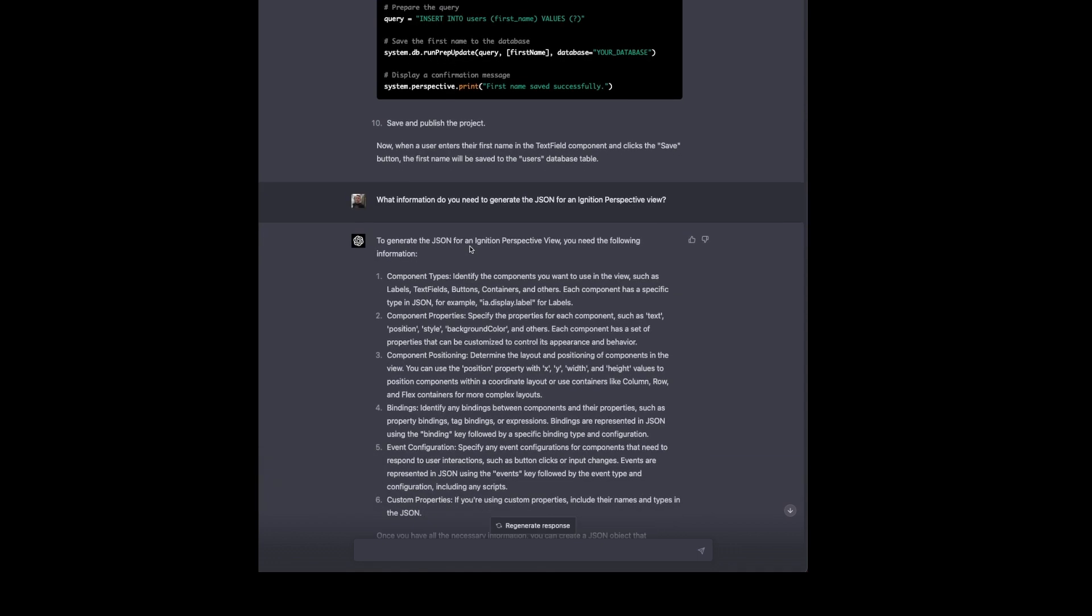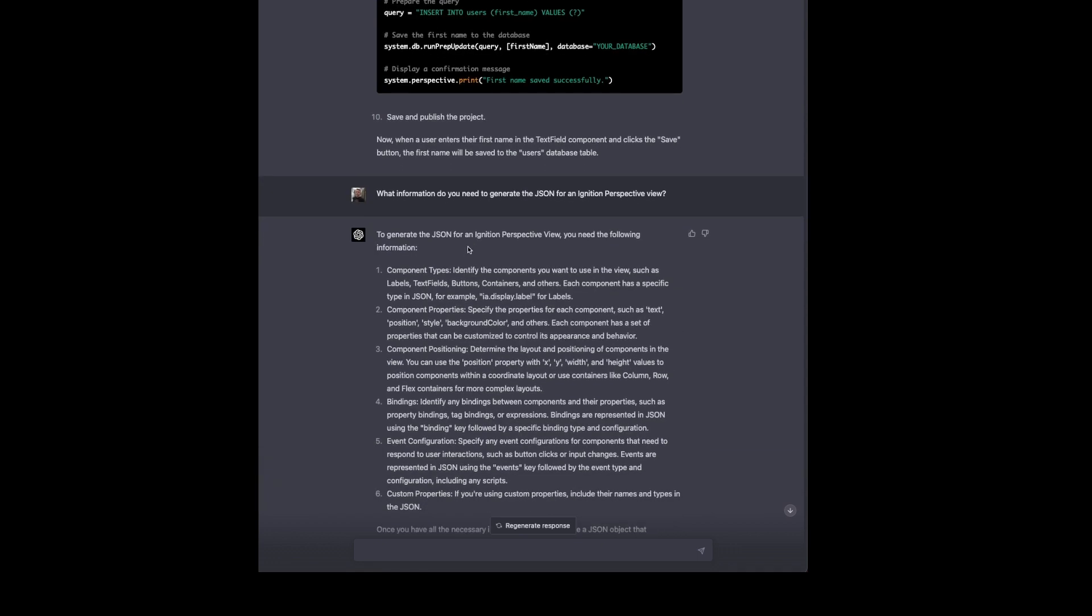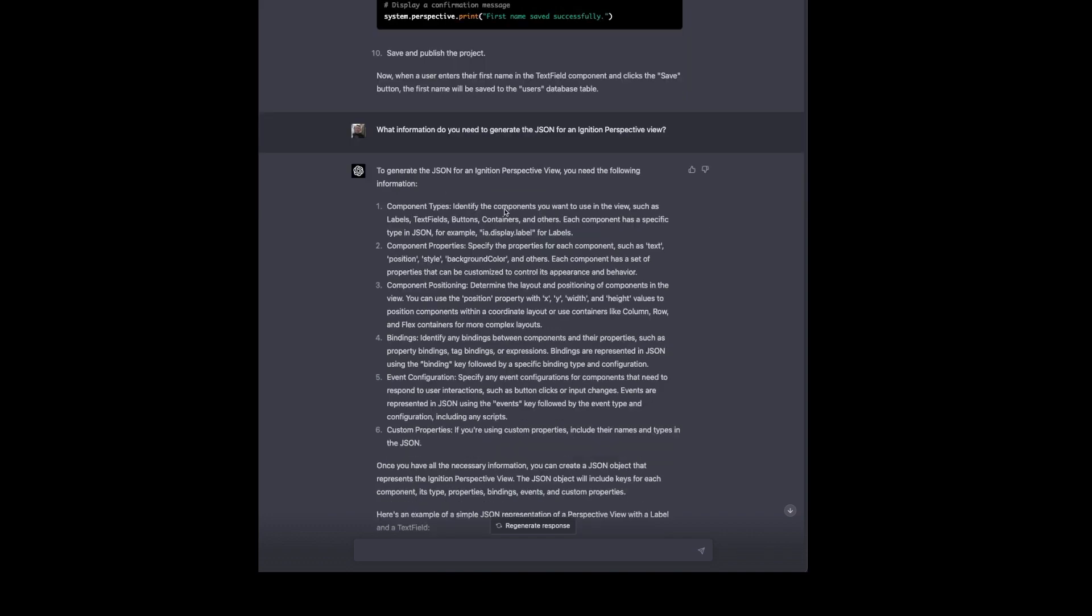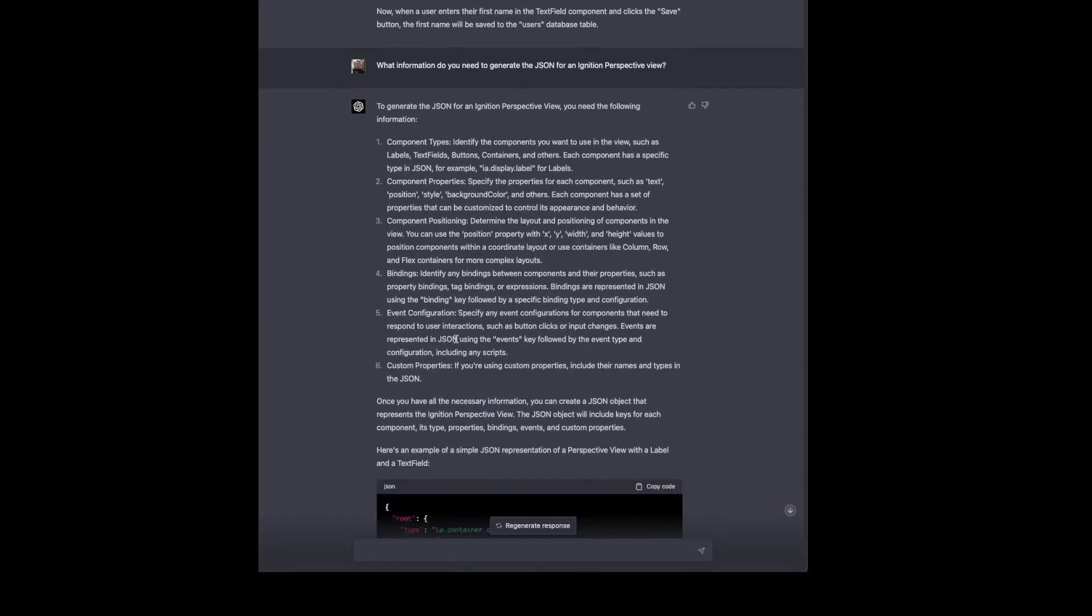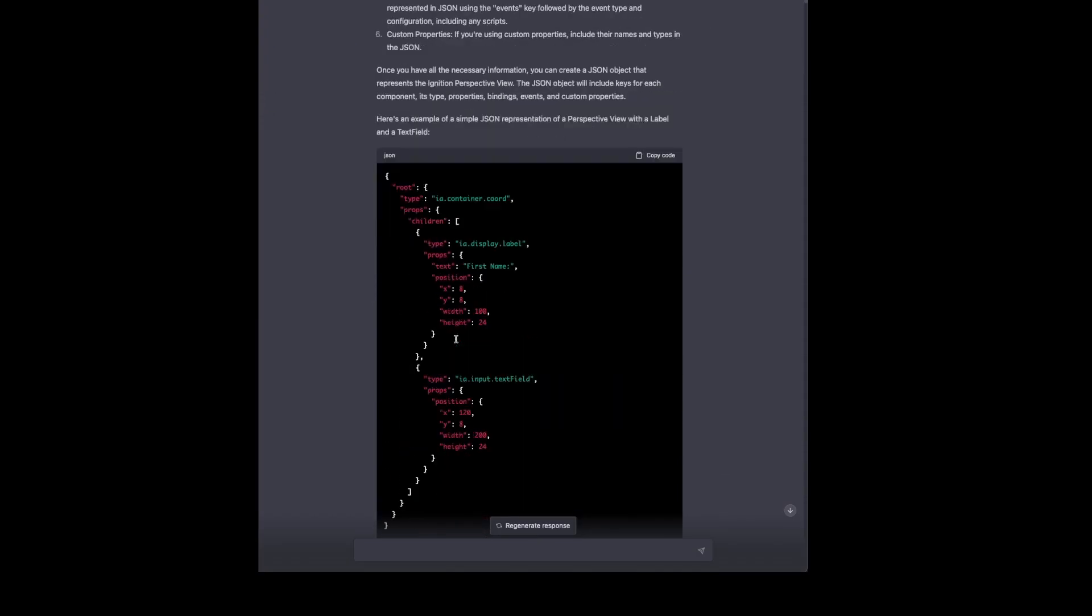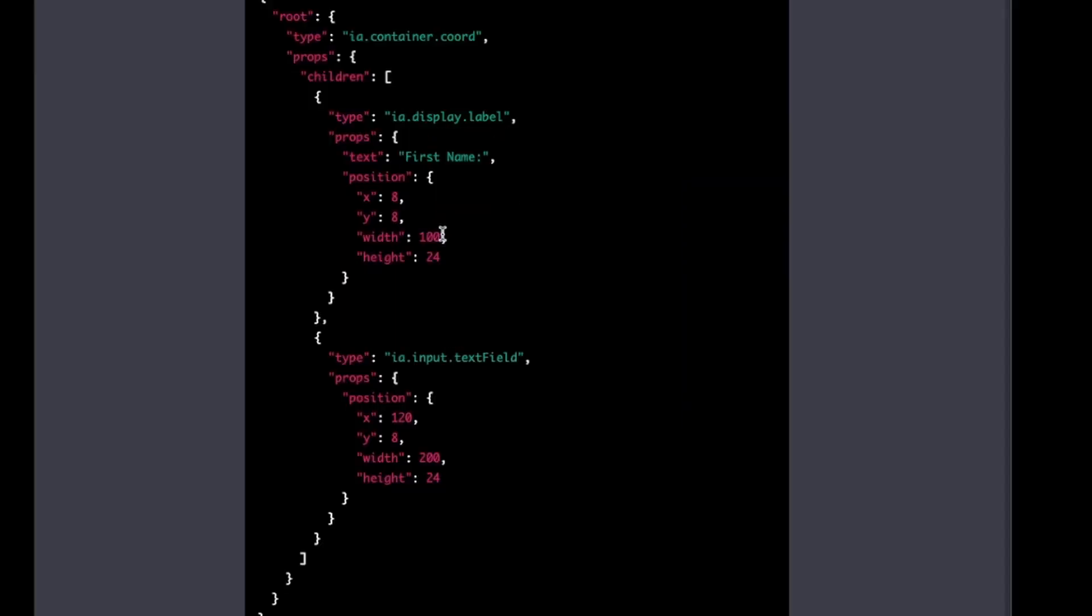So we're going to ask it what information ChatGPT needs to generate the JSON for an Ignition Perspective view. And that's going to give us an example of everything that it would need to see to do that for us. Component types, properties, positions, any bindings, etc. And then it gives us a basic view example here. We're going to notice a few different problems with this. The way you would find those out is build a view in perspective, export the JSON and compare it to what you see here.